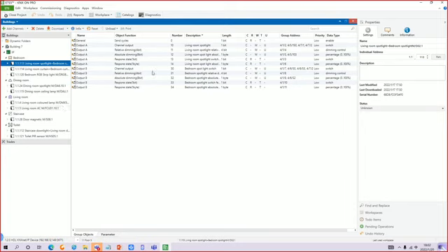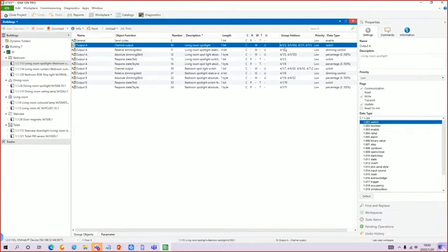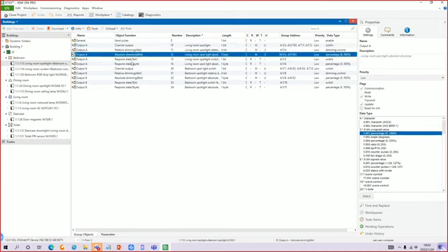From here, we can see the living room spotlight is channel 1, and the group address is 412. And we need to input the channel output group address, the absolute dimming group address, and the response state, which is 1 bit and 1 byte.